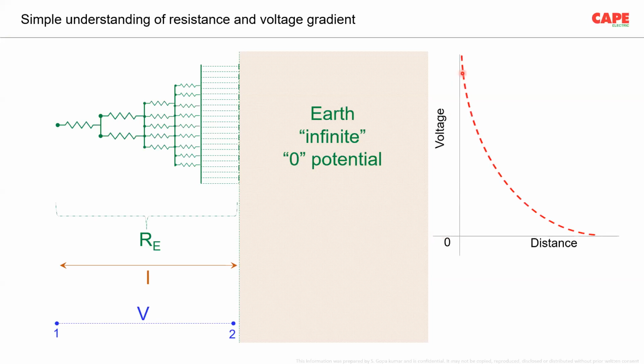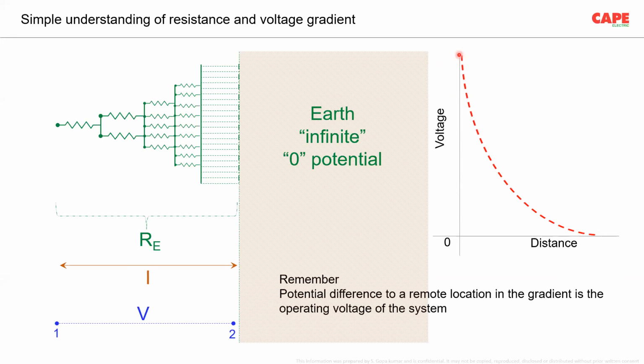At the point of the fault, whenever the current starts flowing, the voltage is at its peak, and this peak is equal to the operating voltage of the circuit which is in fault. Let us say, for example, the fault is created by a 230 volt line. A 230 volt line is in touch with the earth. In that case, the peak of the voltage is 230 volt. I repeat this again: whenever there is a fault in a 230 volt line, the peak of the voltage gradient is only 230 volt.